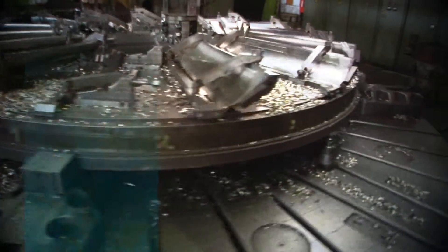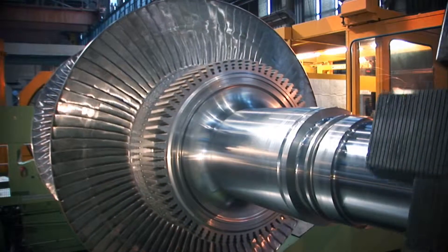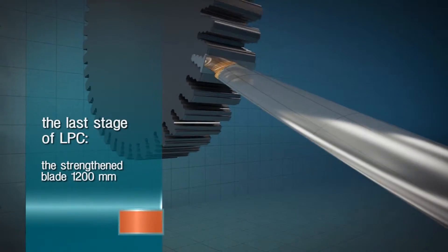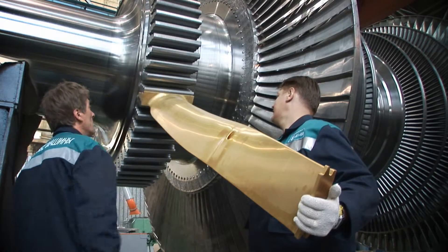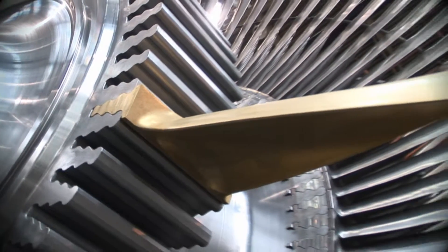The special shape of the fixed blades provides optimal steam distribution along the blade length and an efficiency increase for the high and low pressure cylinders. We've designed a new moving blade for the last stage of the low pressure cylinder. Titanium used in its manufacture provides remarkably high strength characteristics. The surface of the turbine last stage moving blades is covered with a high strength protective coating of titanium nitride, which prevents erosion wear.